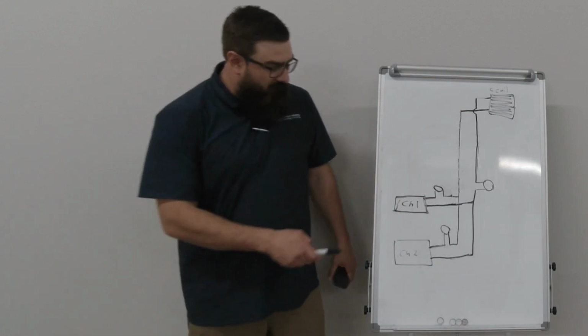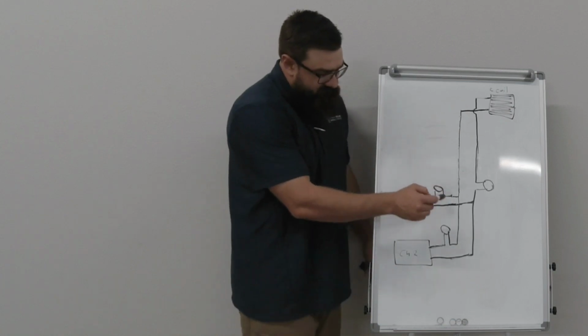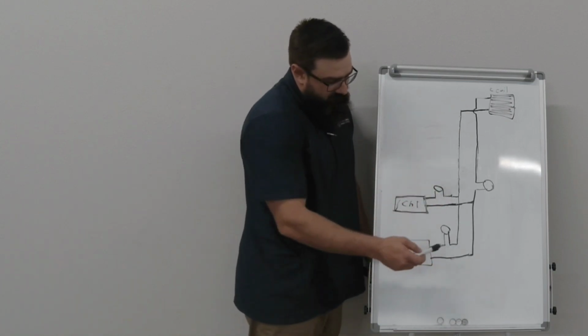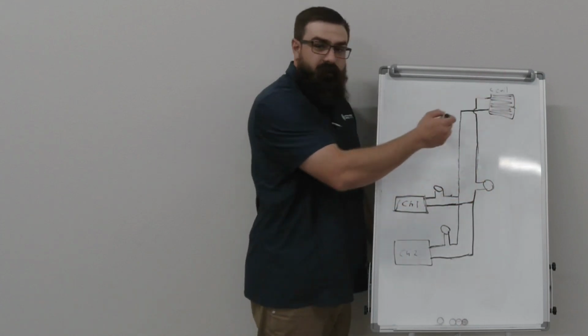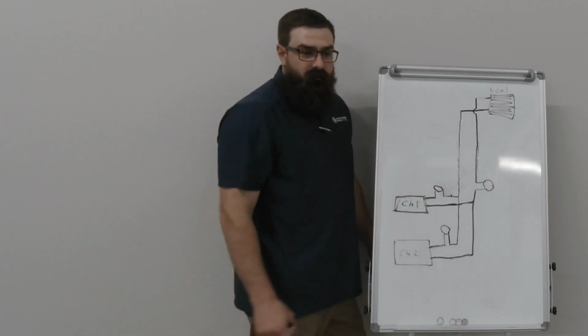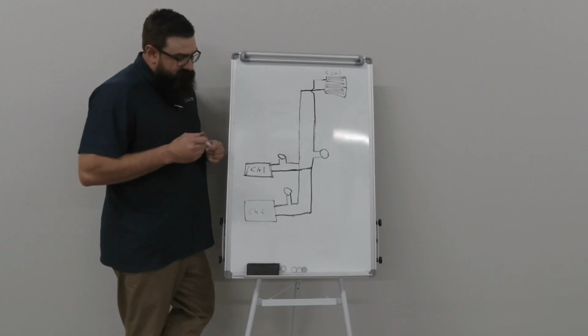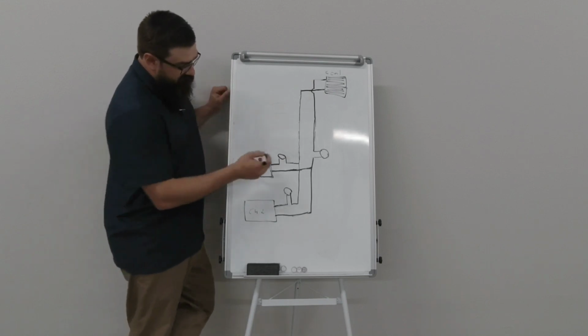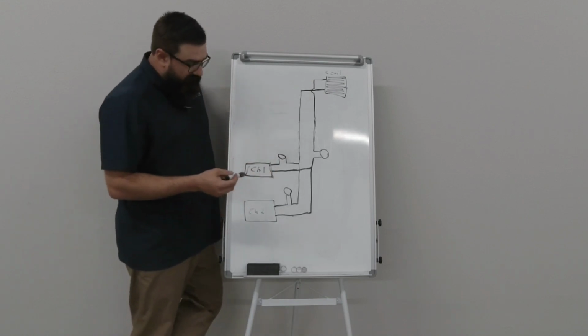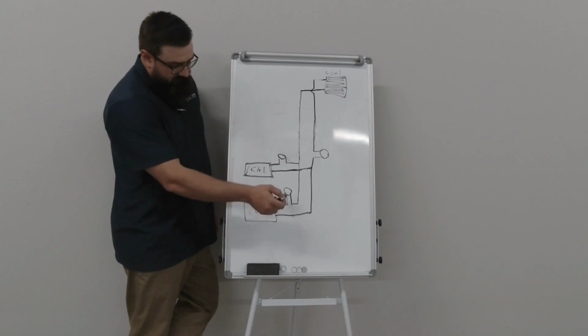So you can run smaller pumps on your chillers to circulate water through the chiller, and then they feed in, and then the big pump pushes water through the building in order to send it to all the floors.